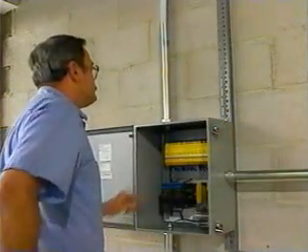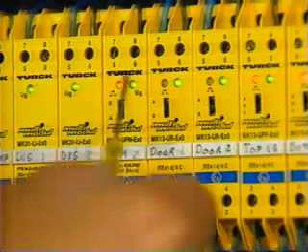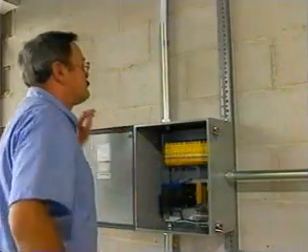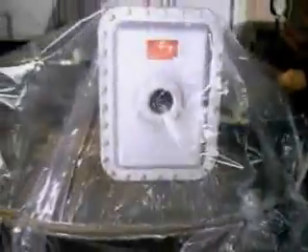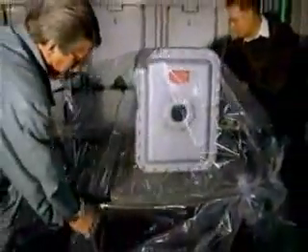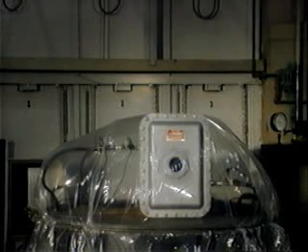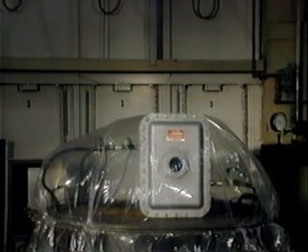Compare that to purged air rooms and explosion-proof enclosures, which demand meticulous maintenance. A careless mistake there can have disastrous results. To demonstrate the importance of proper maintenance, we prepared a special explosion-proof enclosure with a window and a spark plug. We placed the enclosure in a Group B environment and simulated how explosive gases can seep into an enclosure during temperature change or maintenance. When current is sent to the spark plug, we see how a properly maintained enclosure contains the explosion.